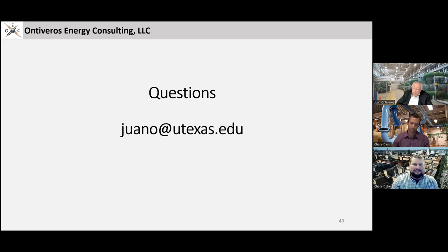Yeah, so the way we use the thermal storage, the 80,000 ton hours, basically provides cooling for the campus for about 8 hours. I think that was the way it was designed. However, it's rare that you need that, as in you've lost cooling and you need to provide the cooling of the campus. Our peak was 30,000 tons, so you can serve the majority of it with the thermal storage.